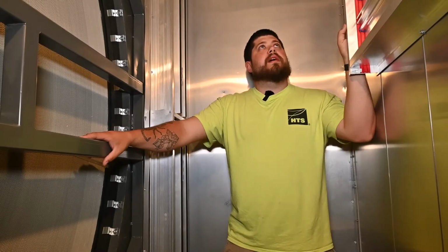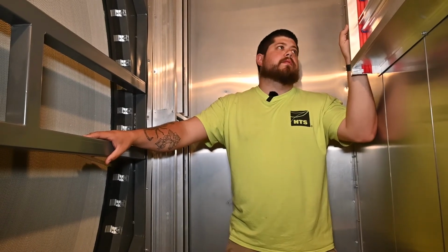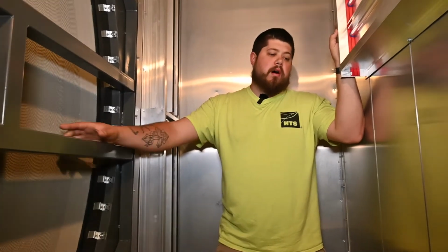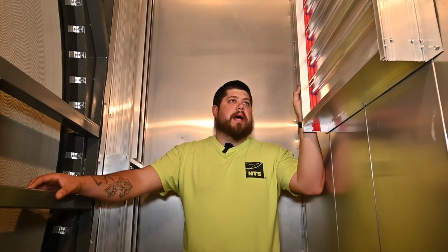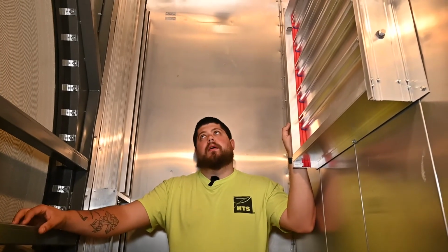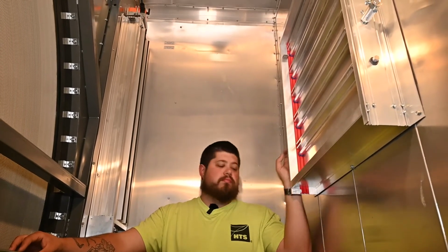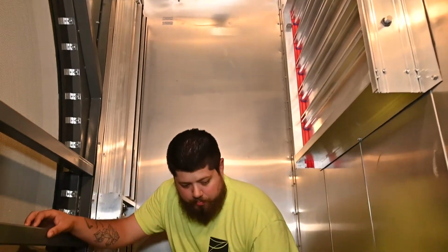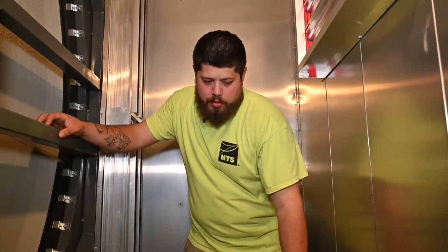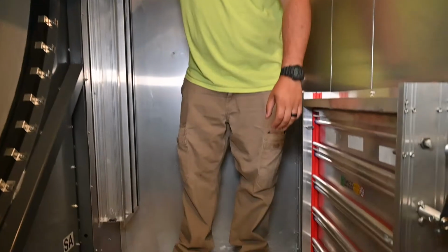In this section here, we have our supply fan gravity dampers. This is to allow, if needed, one fan off for any reason. If a fan goes bad, it'll stop it from backspinning. Ideally, it should work very well. As you can see, a little bit of pressure will open them up, but they'll close once they lose the actual grip of the fan.